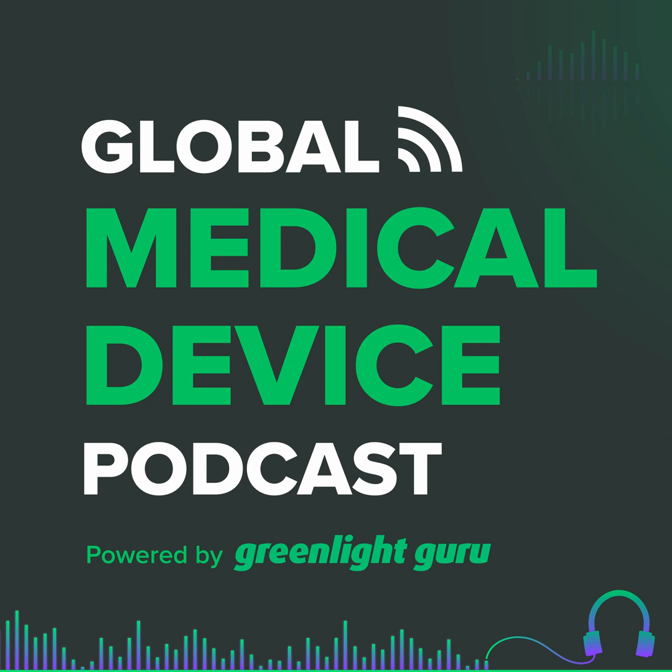I do think so. Change control in general, like you said, it's a risky topic, so one that a lot of people don't do well. So once you get that down, if you already know the changes that you plan to make, then absolutely, I would want to get that in front of the FDA sooner than later. And this is the essence of this quote unquote new PCCP program. Basically, it allows you, as part of your original submission, whether it's a 510K, de novo, PMA, whatever, to get a change to your device approved.